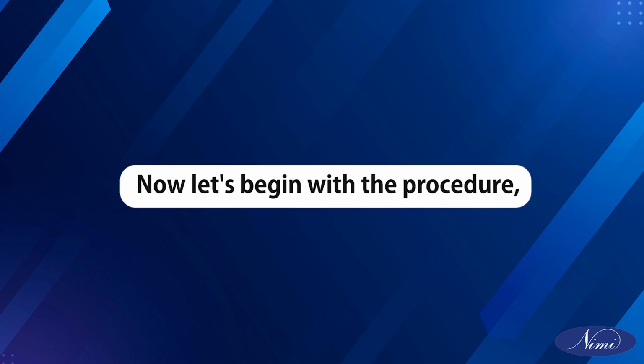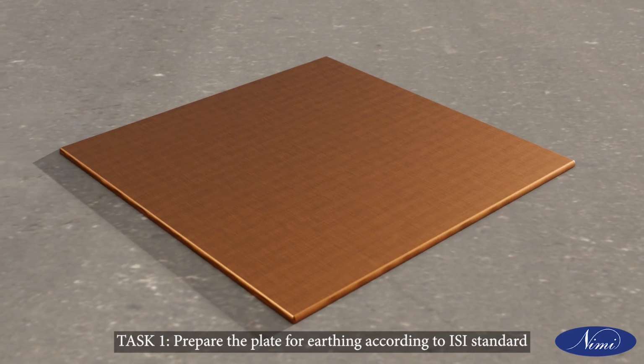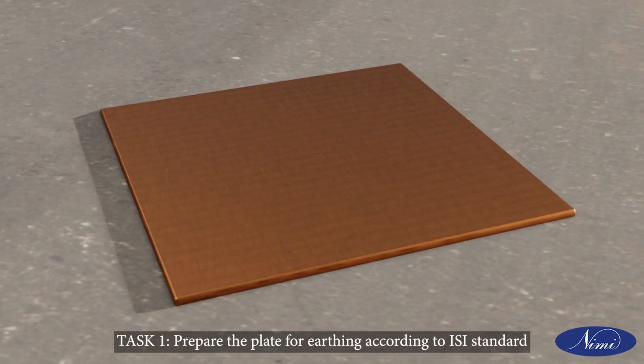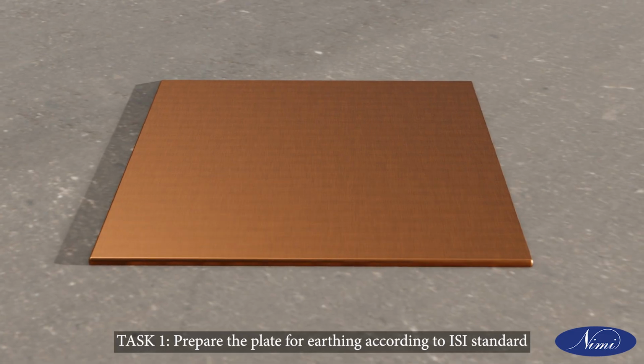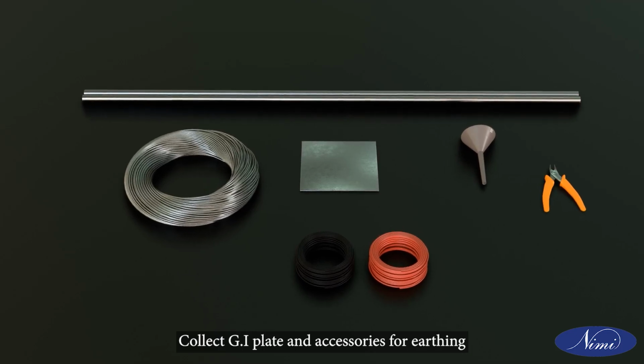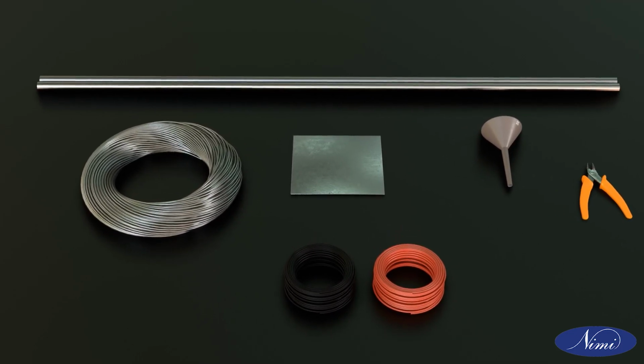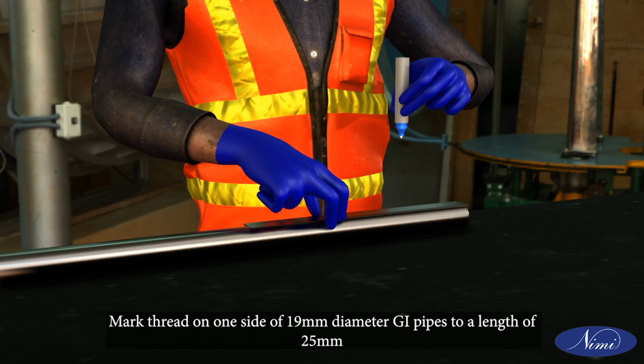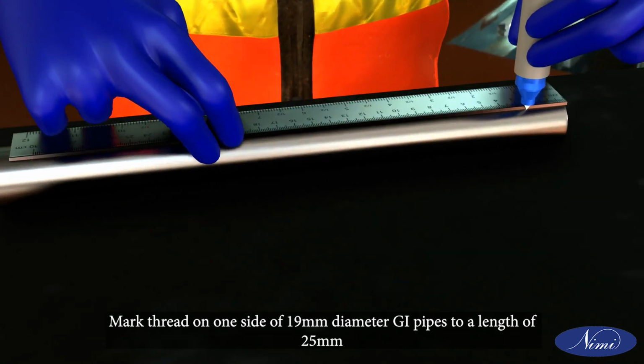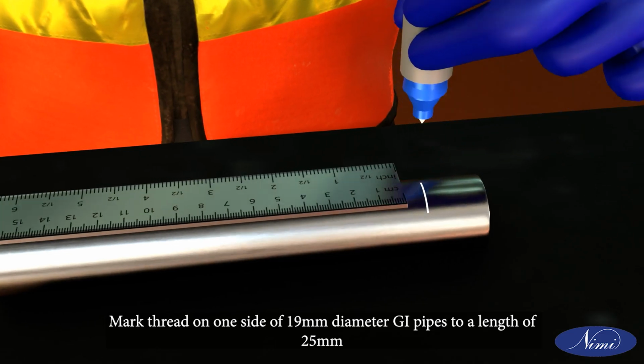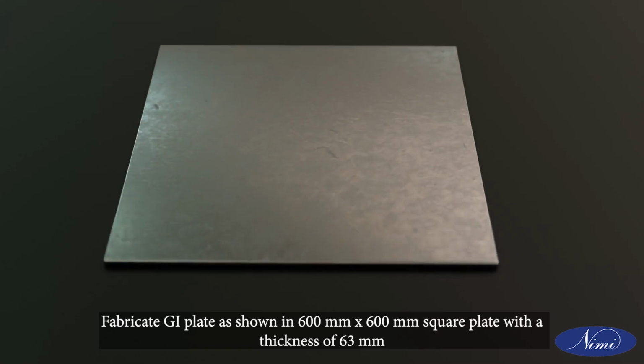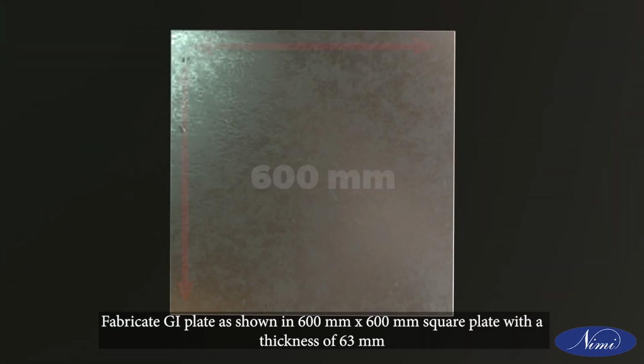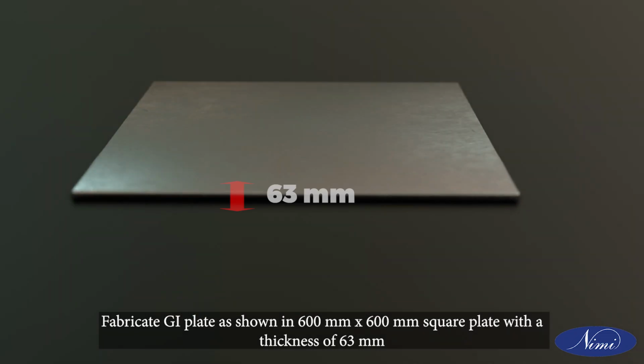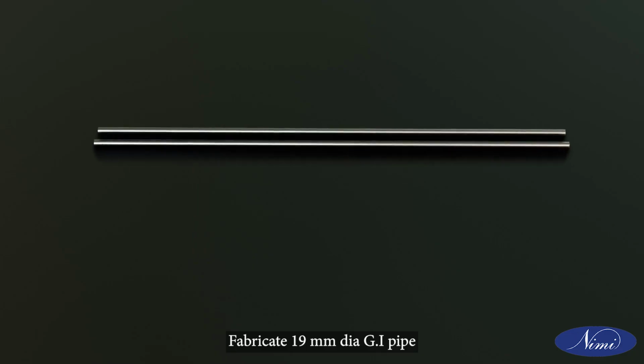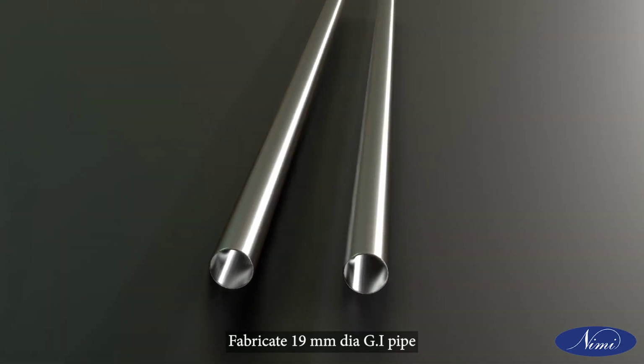Now, let's begin with the procedure. Task 1. Prepare the plate for earthing according to ISI standard. Collect GI plate and accessories for earthing. Mark thread on one side of 19 mm diameter GI pipes to a length of 25 mm. Fabricate GI plate as shown in Figure 1, 600 mm into 600 mm square plate with a thickness of 6.3 mm. Fabricate 19 mm diameter GI pipe.